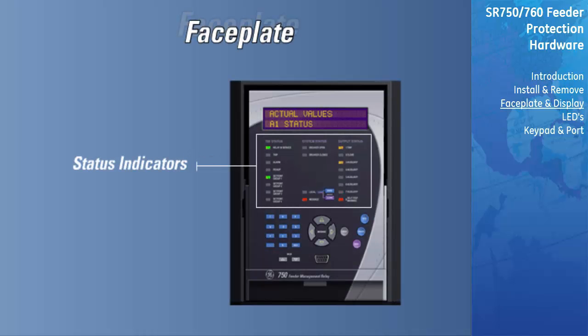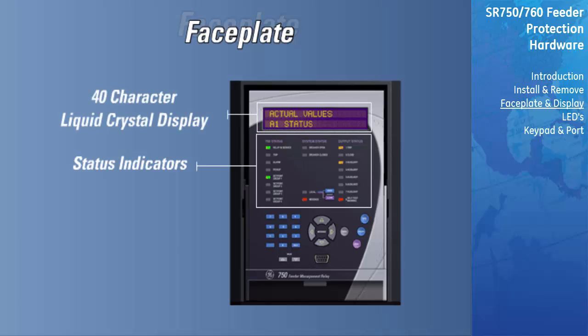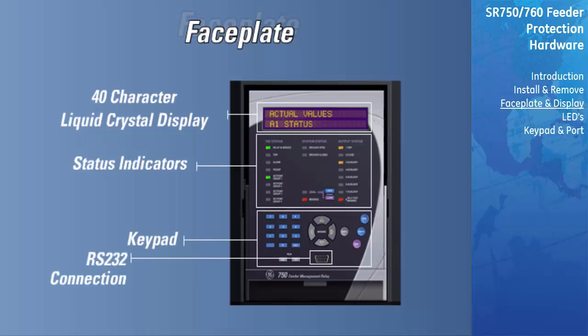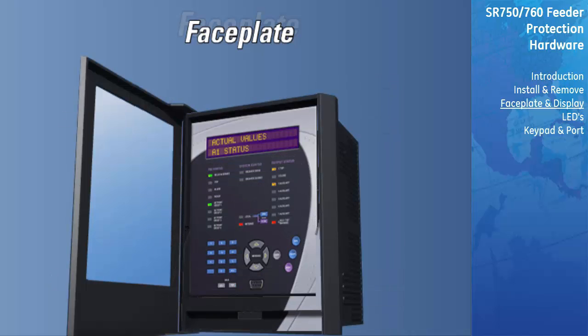Status indicators for the 750 system and output relay status, in addition to a 40-character message display and keypad, allow control, programming, and status monitoring without the need for a computer. However, the conveniently located front RS-232 port allows easy connection to a computer for programming and monitoring. The relay's draw-out handle has provision for a wire lead seal to detect unauthorized removal.